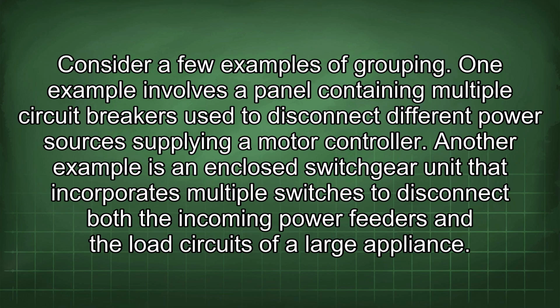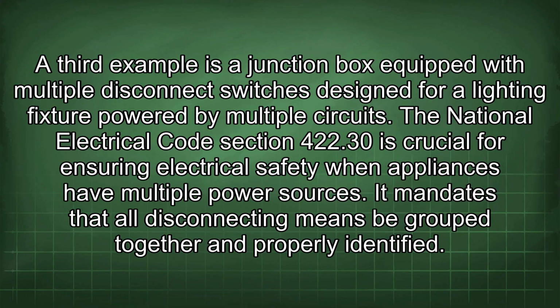One example involves a panel containing multiple circuit breakers used to disconnect different power sources supplying a motor controller. Another example is an enclosed switchgear unit that incorporates multiple switches to disconnect both the incoming power feeders and the load circuits of a large appliance. A third example is a junction box equipped with multiple disconnect switches designed for a lighting fixture powered by multiple circuits.